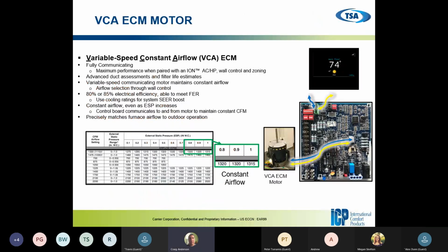So, variable speed constant airflow. Like I said, it's a communicating motor. It's in our 97 and 96%. This motor communicates with the thermostat and it communicates with the board. What we mean by constant airflow, as we'll notice down here at the bottom, is that the static pressure is changing, but the airflow, or CFMs, is not changing. This motor will do everything in its power to give you a constant airflow, a constant CFM, regardless of the static pressure. So keep in mind, if you have this furnace and we have real bad ductwork, this motor is going to work hard because it's going to try anything in its power to keep a constant airflow.